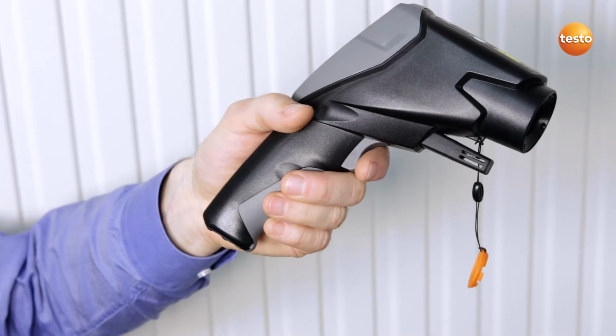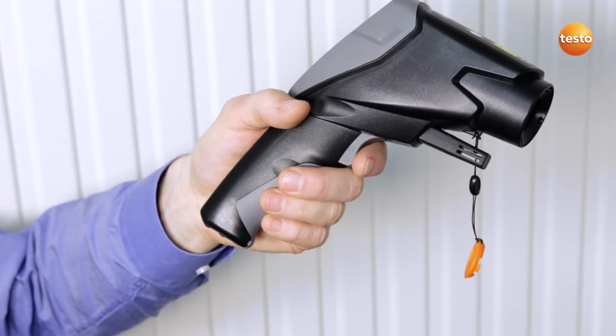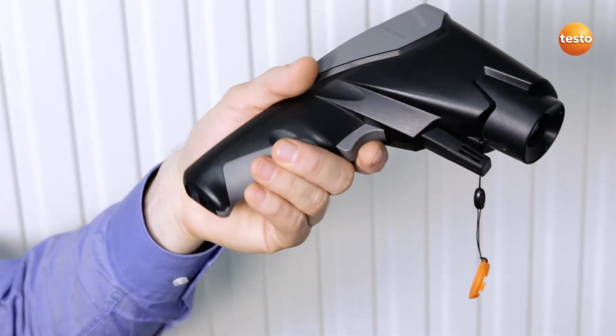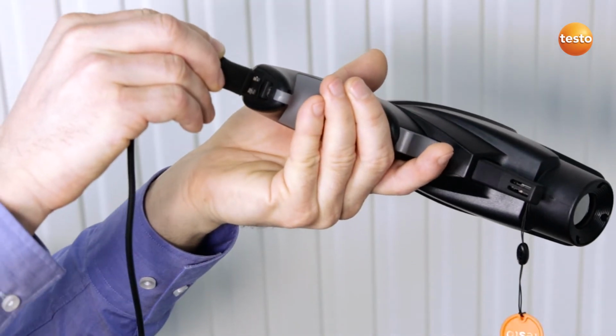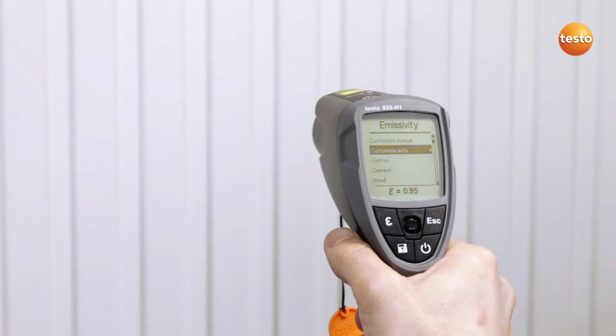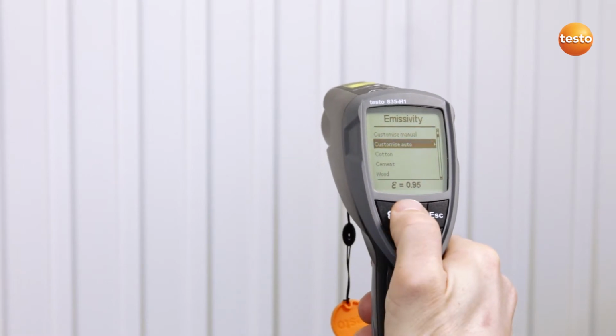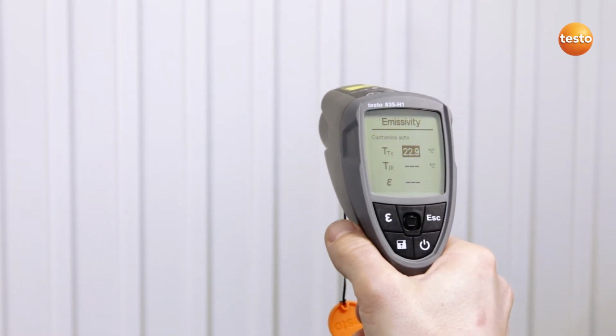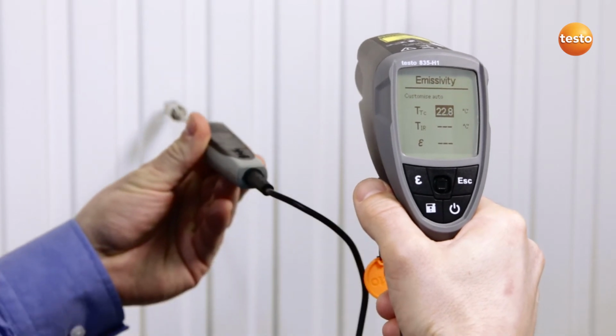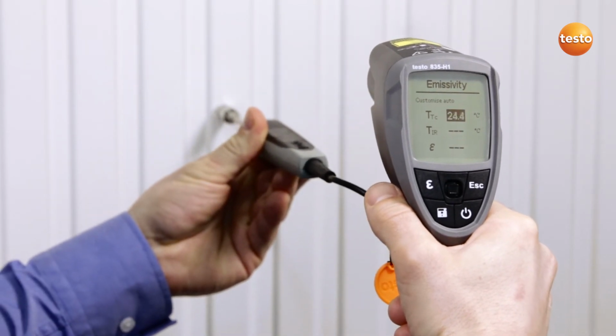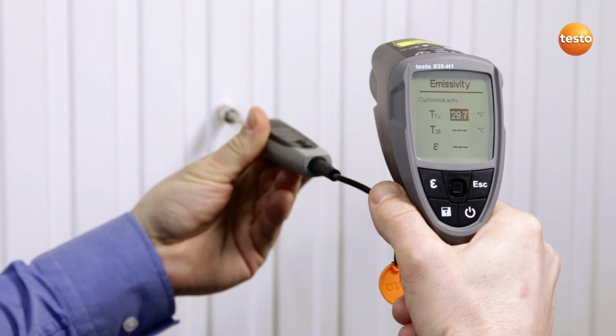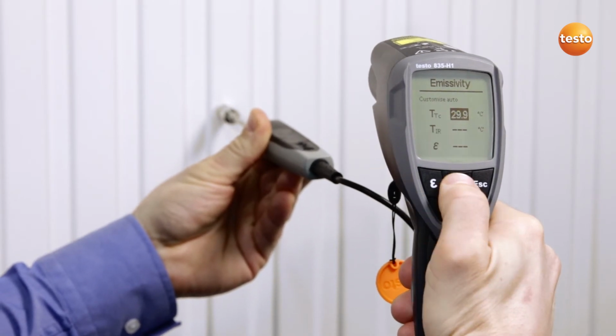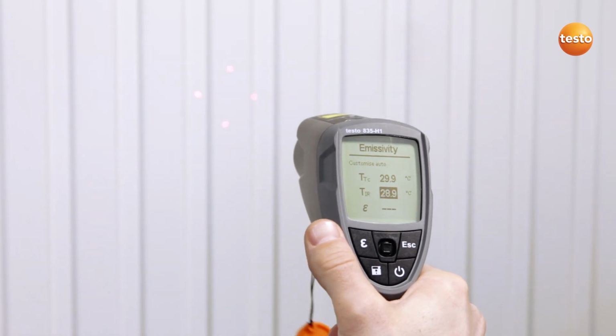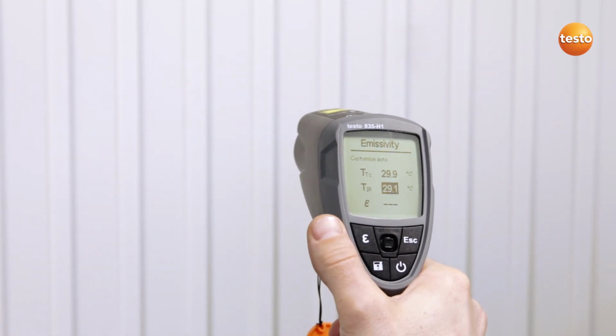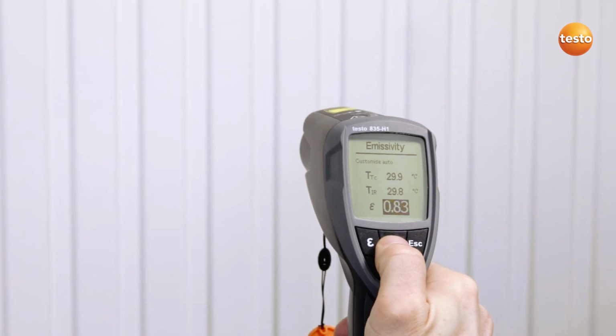In order to determine the emissivity of a measurement object, you require an external probe. Please connect this to the underside of the instrument. Now click on Customize Auto and carry out two measurements. First with the external probe, and then with the infrared measuring instrument. The calculated emissivity then appears. Take this over by clicking with the joystick.